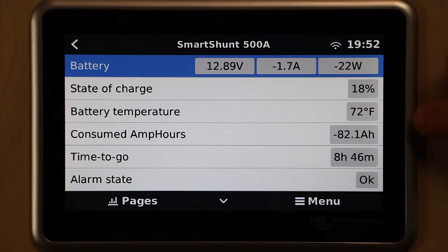Looking at temperature, the SmartShunt reads 72 Fahrenheit, and the battery has acclimated to the room temperature here. The Lynx Shunt reads 77. So SmartShunt said 72, Lynx Shunt said 77 — I can tell you it's 5 degrees too high on the Lynx Shunt. You'd want to keep that in mind when setting any alarms, like a shutdown alarm based on battery temperature, and account for that discrepancy.